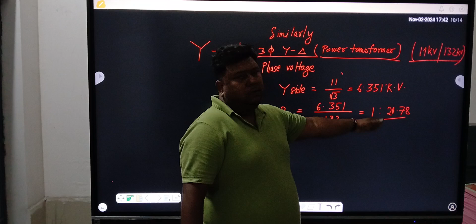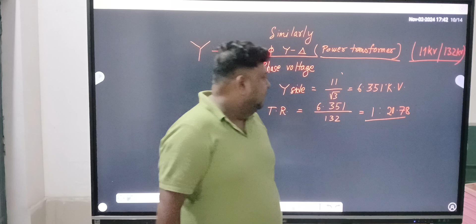1:20.78. And as I have told, this value should be not exactly but approximately same for each and every tap test conditions. Suppose we are testing it on tap 2 or 3 whatever, and further we are going to test it on tap 5, tap 7, tap 8 or whatever tappings, the same ratio should be there. Same means approximate value is considered. That's it for voltage ratio or turn ratio test.